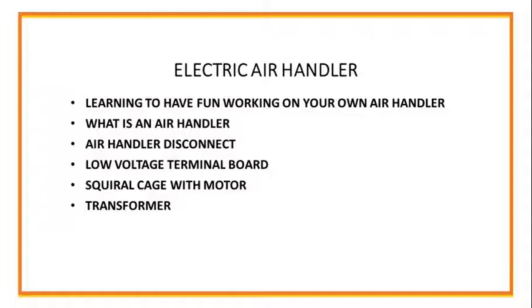What is an air handler? We'll discuss what an air handler actually looks like. Air handler disconnect. We have to make sure you turn off the power. Make sure you have power to your air handler. Low voltage terminal board. We'll discuss a low voltage terminal board coming from your transformer and your air handler, and also it'll be going out to your outside unit. Squirrel cage with motor. I'll show you the squirrel cage and everything that's attached to the transformer. It usually is a 220 volts to a 24 volt step down.